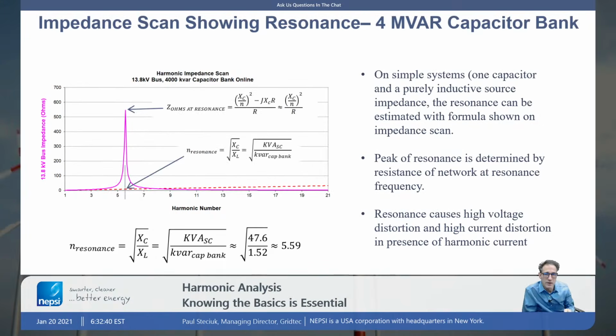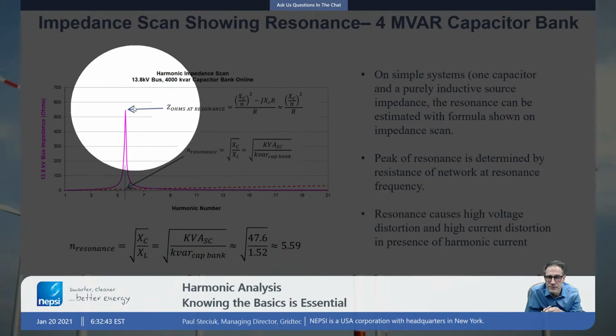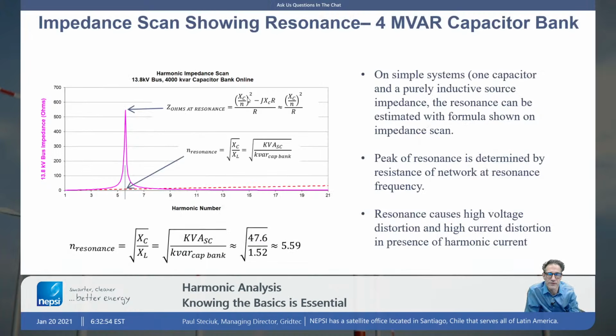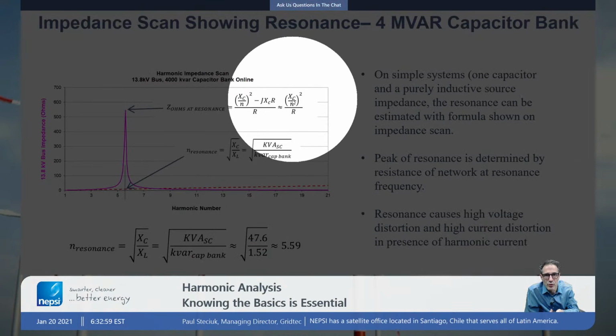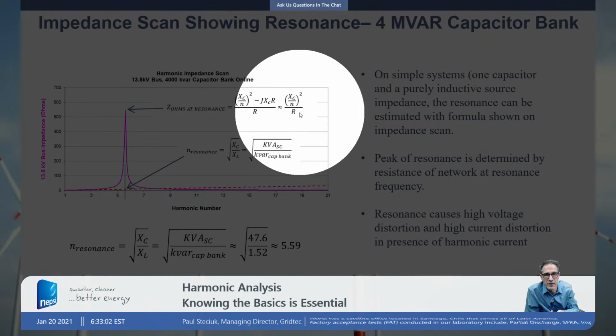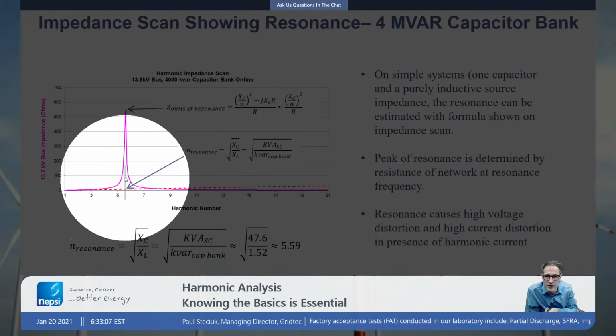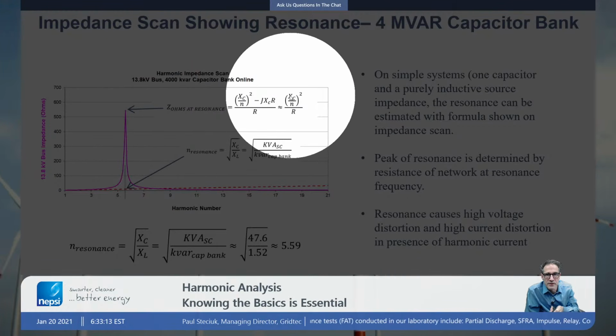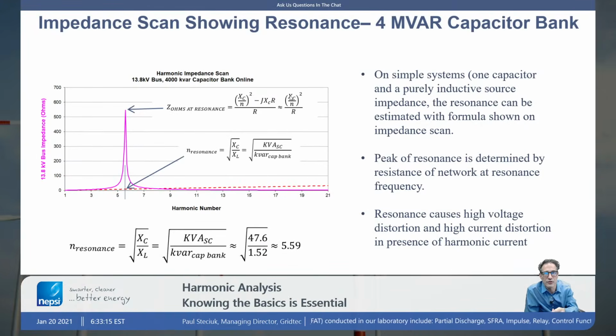The peak of this impedance curve here is defined by this equation. So you can kind of go through the calculations by hand. It is complex numbers, so it's a little bit more difficult to do. But this peak here is defined by a value of X of C divided by n, squared, and then divided by the resistance of the network. So in this case, n represents the harmonic resonant point, the peak value. What value of harmonic is it? X of C is the 50 hertz or 60 hertz reactance, and R is the resistance of the network.